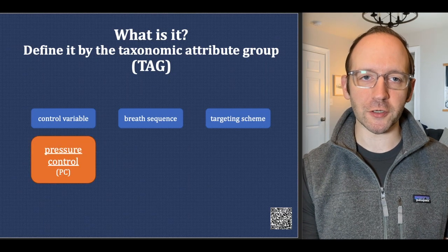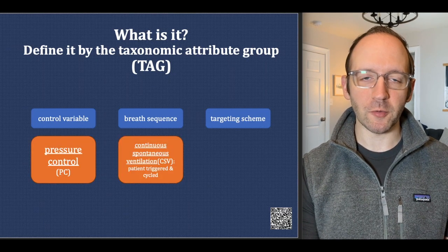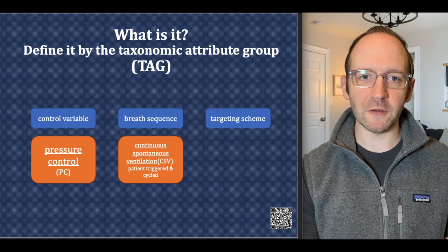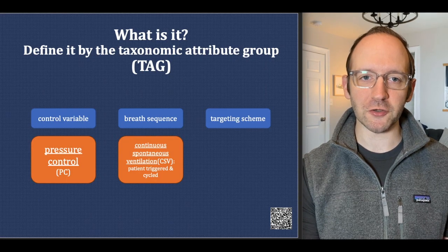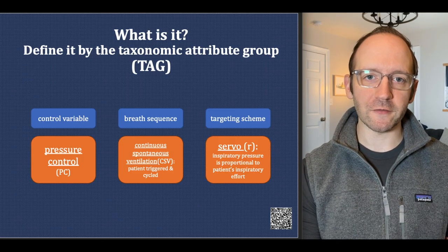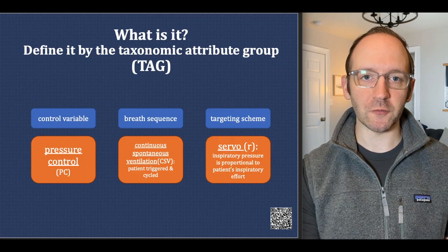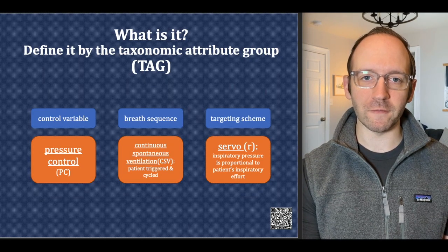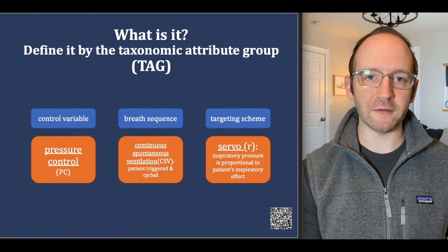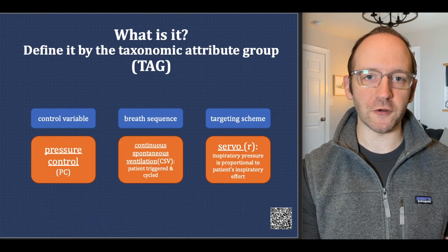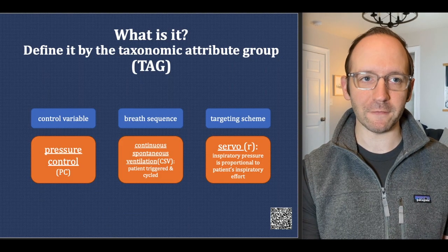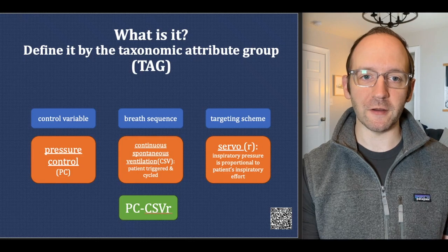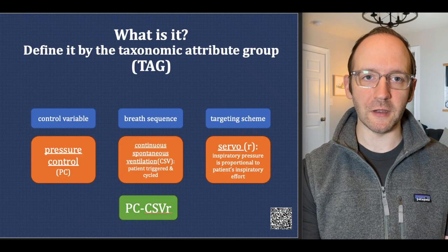For PAV, this is a pressure control type of mode. The breath sequence is continuous spontaneous ventilation, so this is a patient-triggered and patient-cycled mode, similar to pressure support. The targeting scheme is the really interesting thing about this mode — it's called servo targeting, not to be confused with the servo ventilator. Servo targeting implies that inspiratory pressure is proportional to a patient's inspiratory effort. Written together, it is PC-CSV-r.